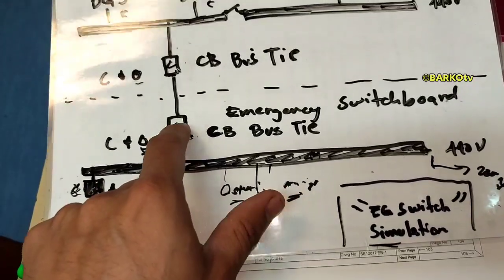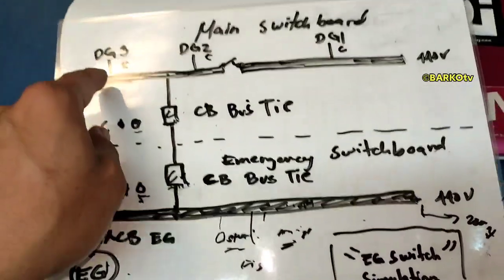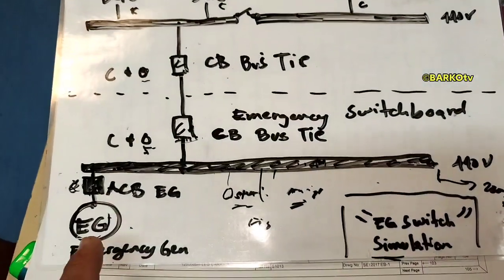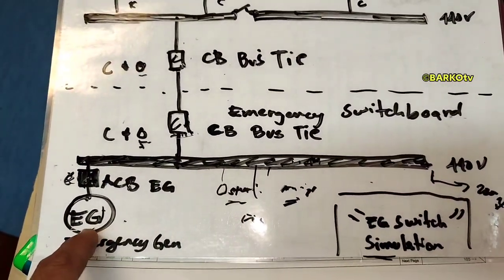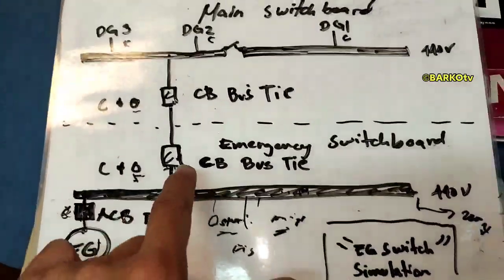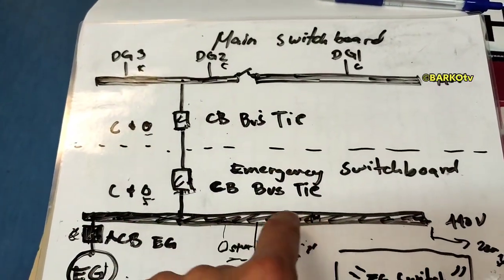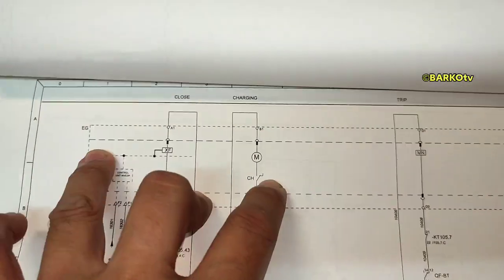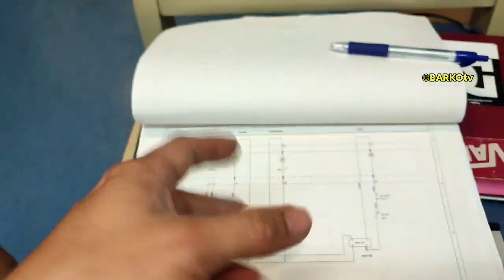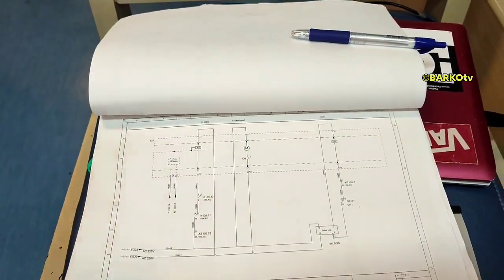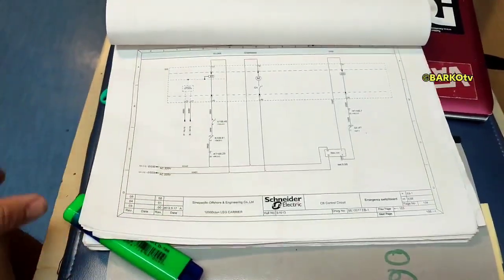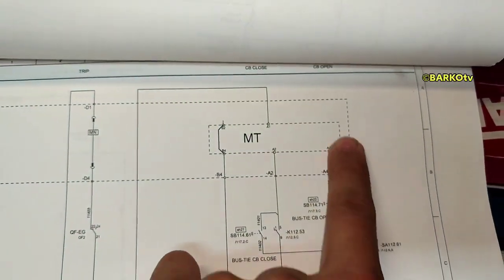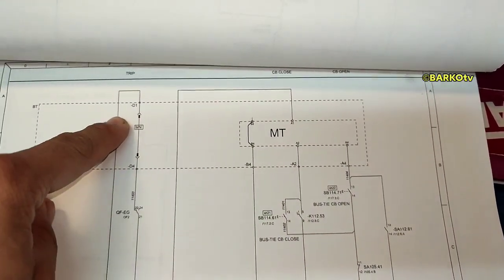If the emergency generator is supplying the bus bar, you cannot open or close the bus tie because it is prohibited to supply the main switchboard to the emergency switchboard while the emergency generator is running. You need to turn off or open the emergency generator breaker before you can switch supply back to the main switchboard. There is a charging motor and this is the solenoid trip for the ACB — the emergency generator ACB. We have separate videos about ACB metasol breakers and draw-outs. This Schneider breaker follows the same process, and this is the CB close and CB open command — the solenoid coil trips the breaker.